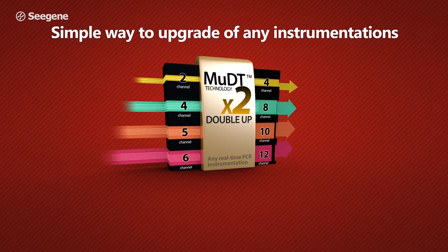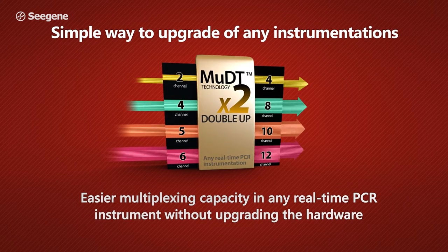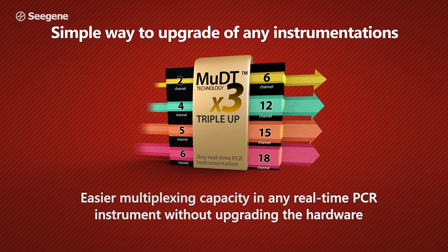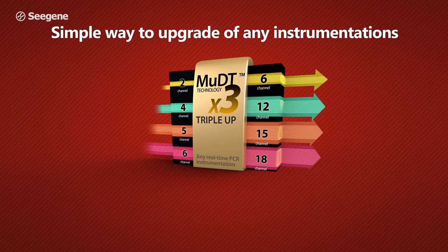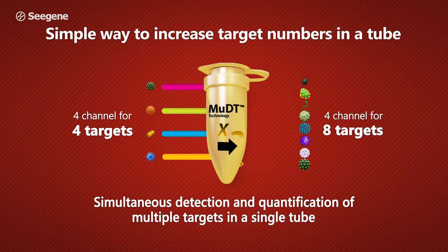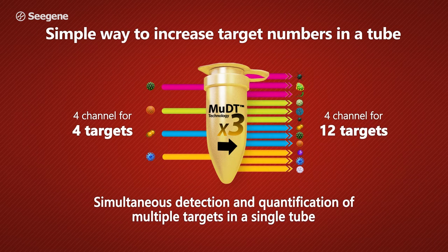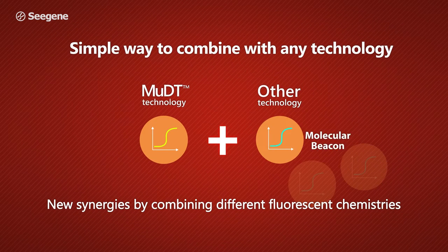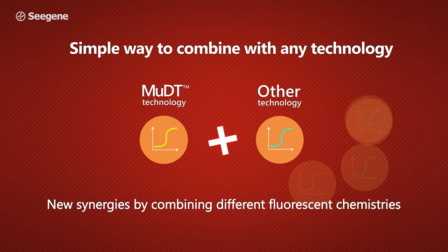MUDT increases the multiplexing capability of any existing real-time PCR instrument without requiring new hardware. MUDT increases the target numbers in a tube up to three times while still providing superior quantitative CT information. MUDT works with any fluorescent chemistry, which can open new possibilities for the molecular diagnostic industry.